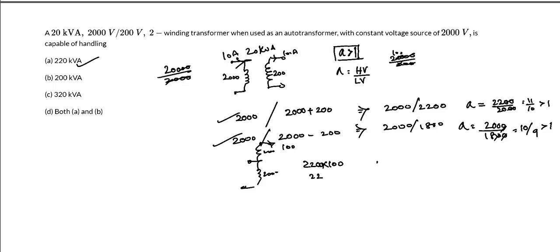Now consider 2000 minus 200, that is 1800. So you have 2000 with subtractive polarity of 200. The current flowing through this winding is 100 ampere. So 1800 into 100 is 180 kVA. Here 180 kVA is not among the options. 220 kVA is the answer. Let's see the next question.